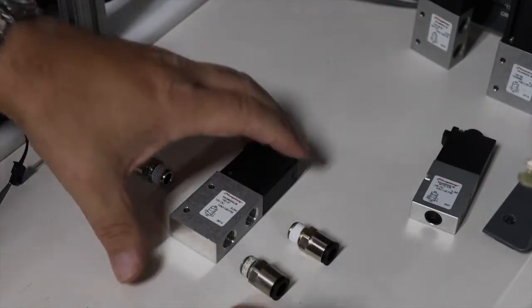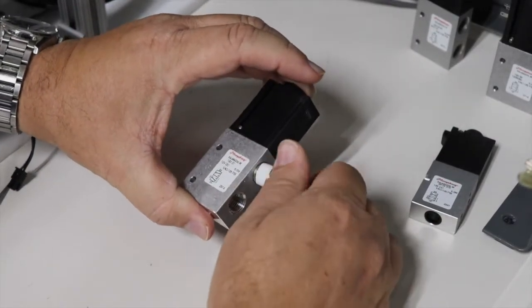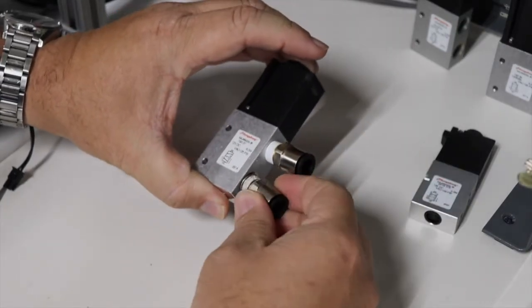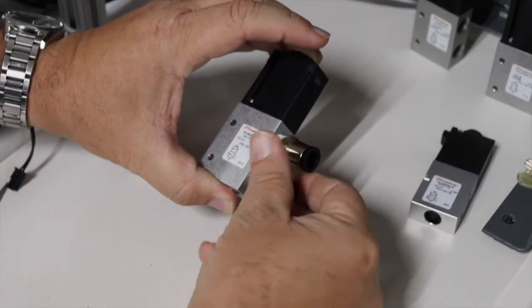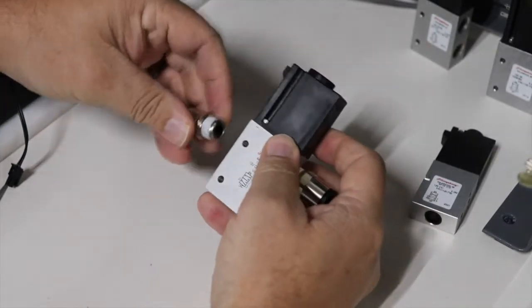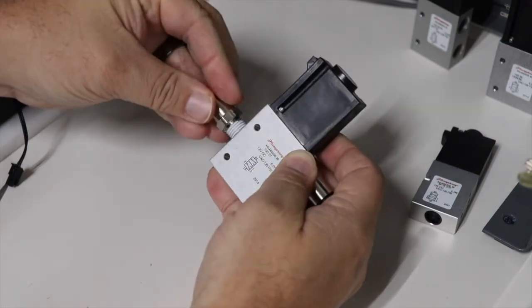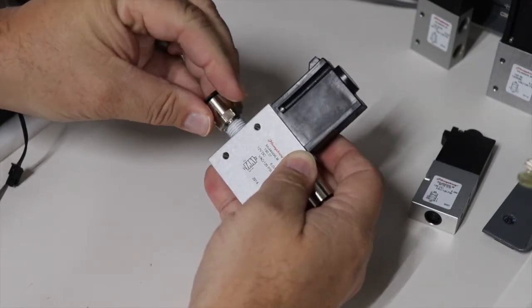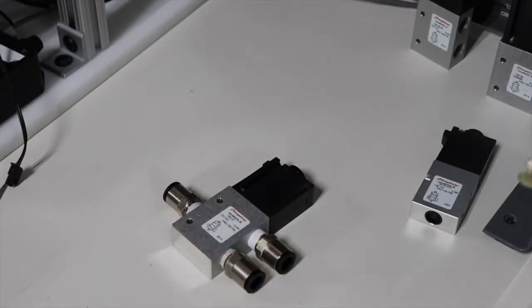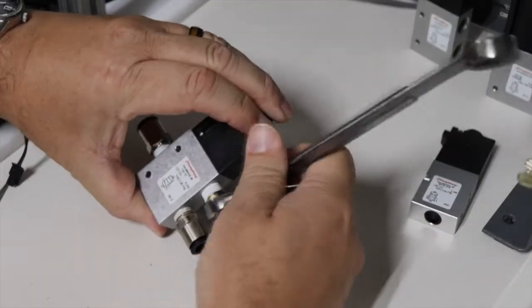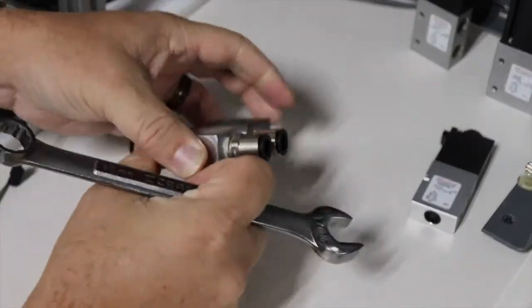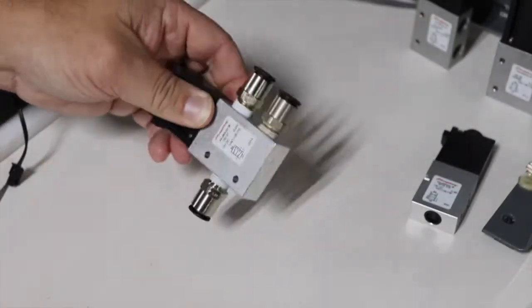When starting the fittings by hand, always feel for unusual resistance from cross threading, contamination, or thread damage. After the fittings are hand tight, use your wrench to finish installation, providing adequate torque to seal the fitting while making sure the appropriate thread engagement and torque levels are met. Please consult the manufacturer or industry guidelines to make sure fittings are adequately and appropriately safely torqued in the valve.